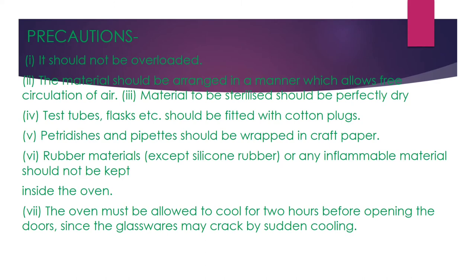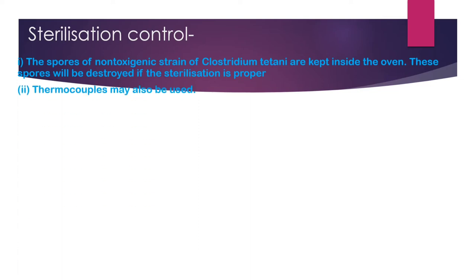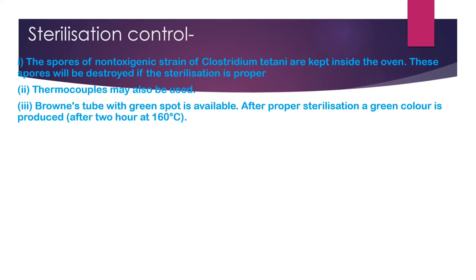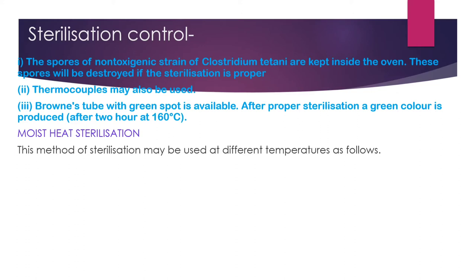For sterilization control, the spores of a non-toxigenic strain of Clostridium tetani are kept inside the oven — these spores will be destroyed if sterilization is proper. Thermocouples may also be used. Brown's tube with a green spot is available; after proper sterilization, the green color is produced.